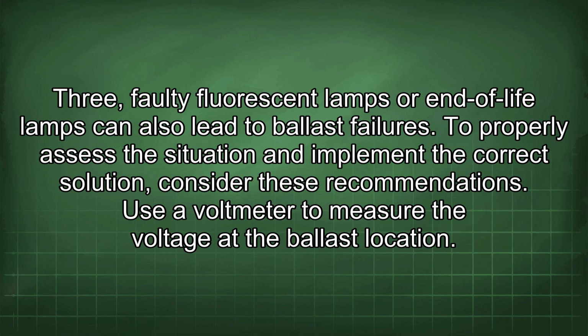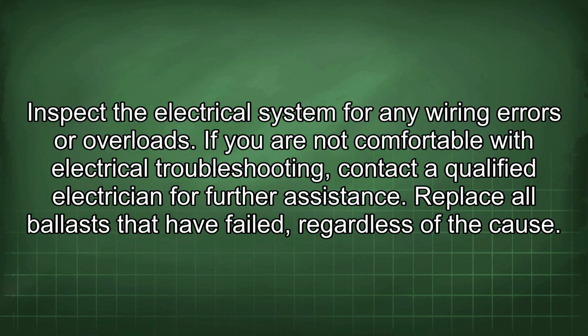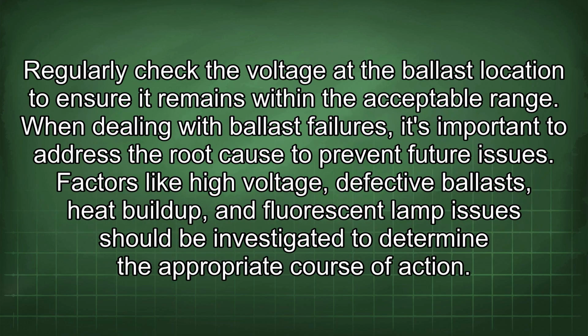To properly assess the situation and implement the correct solution, consider these recommendations. Use a voltmeter to measure the voltage at the ballast location. Inspect the electrical system for any wiring errors or overloads. If you are not comfortable with electrical troubleshooting, contact a qualified electrician for further assistance. Replace all ballasts that have failed, regardless of the cause. Regularly check the voltage at the ballast location to ensure it remains within the acceptable range.